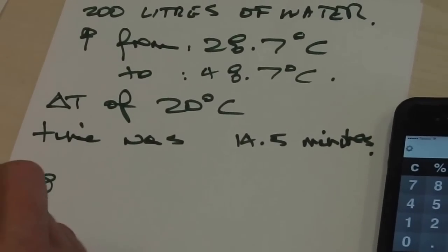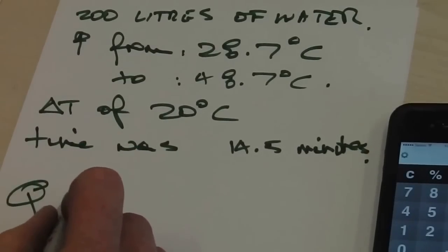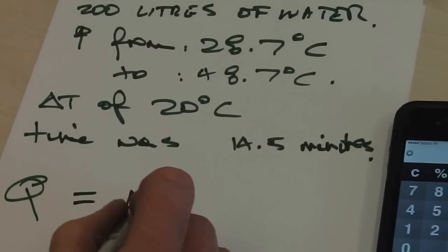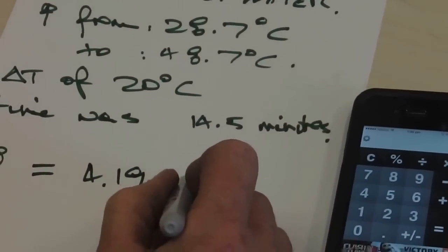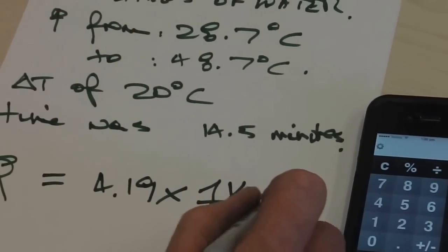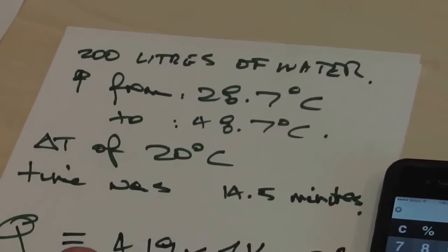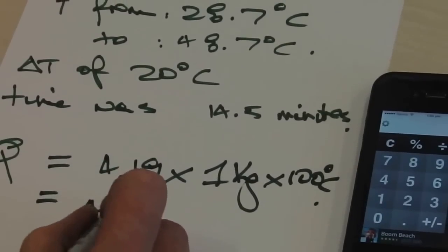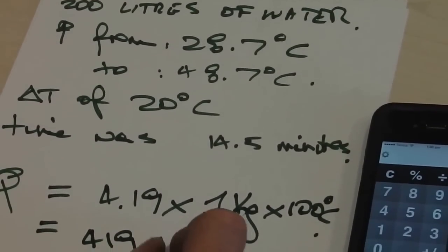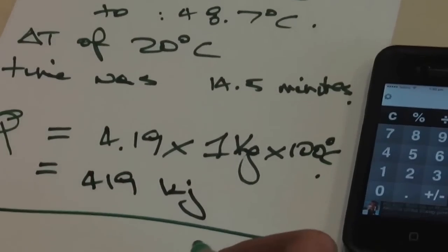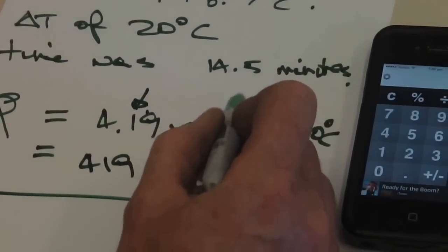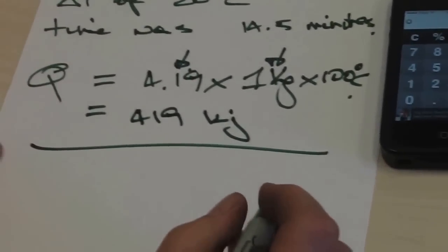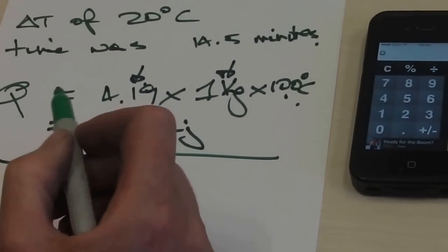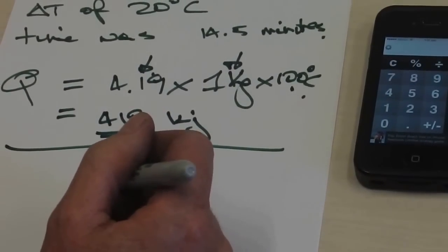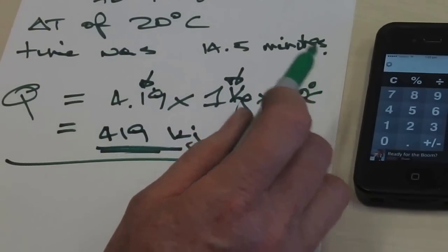So for example, if you wanted to calculate the amount of energy to lift one kilogram of water by 100 degrees C, that would require 419 kilojoules of energy. 4.19 is the specific heat of water. That's the weight of the water. Now again, with normal water, the weight and volume are pretty close anyway. And 100 degrees is the temperature lift you're looking for. So that's the amount of energy you need to lift that 1 kilogram of water by 100 degrees C.